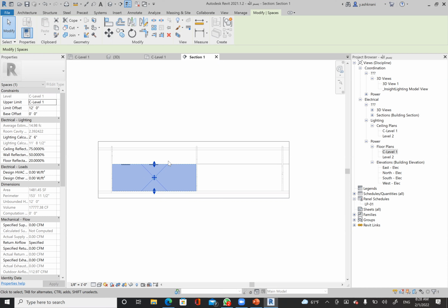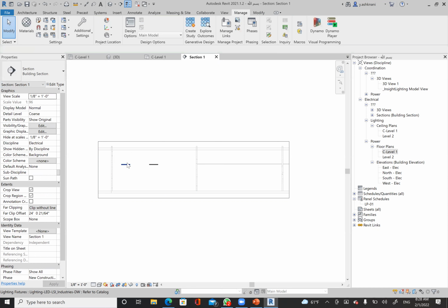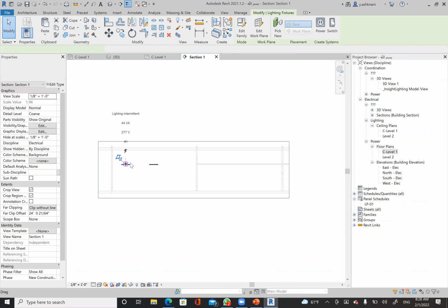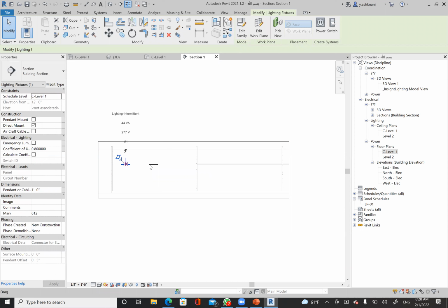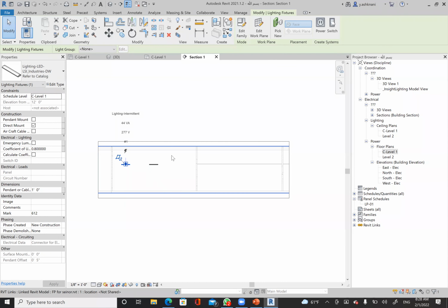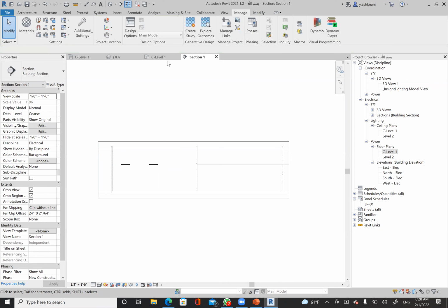So now you have to decide further whether this area is going to remain without ceiling, I mean an exposed area, or with ceiling. If it's without ceiling, then it cannot be suspended like this. This has to go here. Then again, you'll have to increase the space offset more. Then it will be more than 12 feet. You getting my point? Yes. Yeah. So that we can figure out. You saw what the problem was.